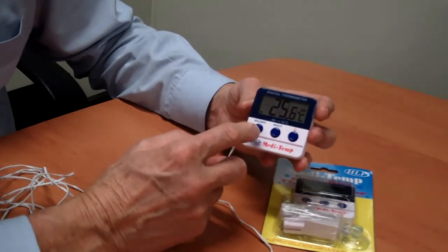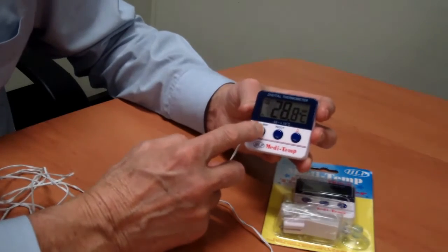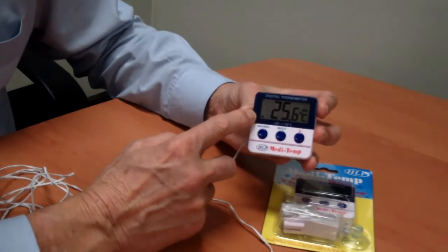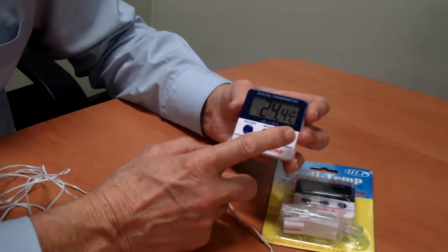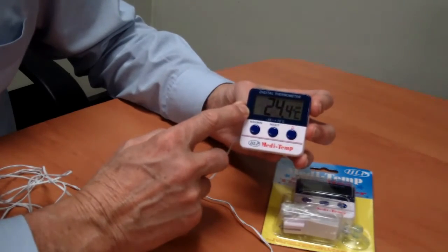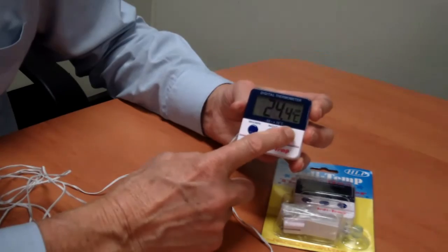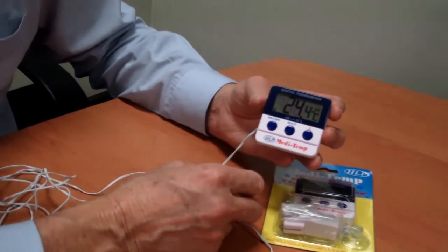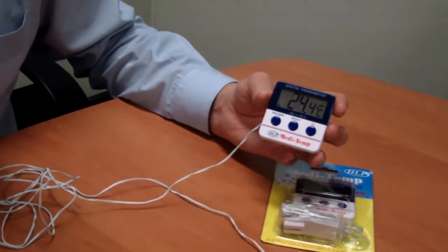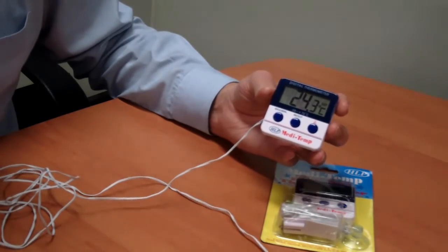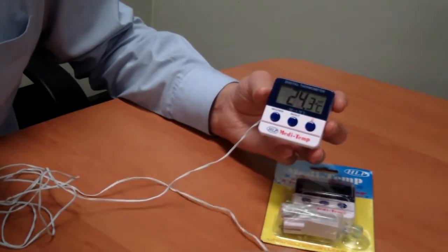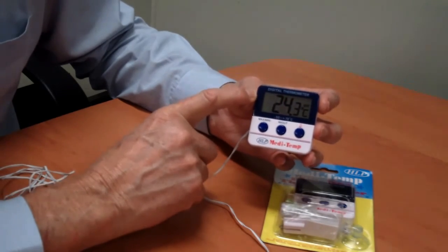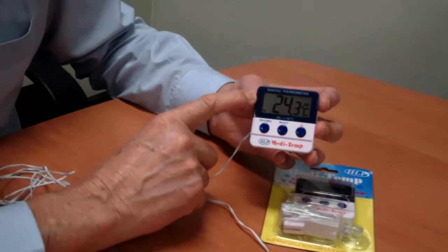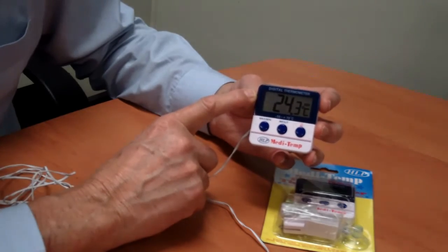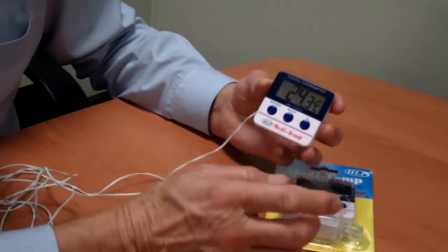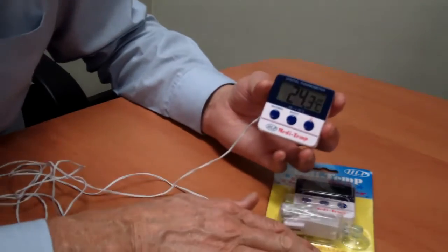So the alarm is set, and the alarm symbol is on. So if I turn the alarm symbol off, I won't get any alarm. If I turn the alarm symbol on, then I will get an alarm. So when that temperature goes above my settings of 2 to 8 degrees, you can hear the alarm beeping, and it will continue to beep irregularly until it's reset. So that's quite easy to set up.